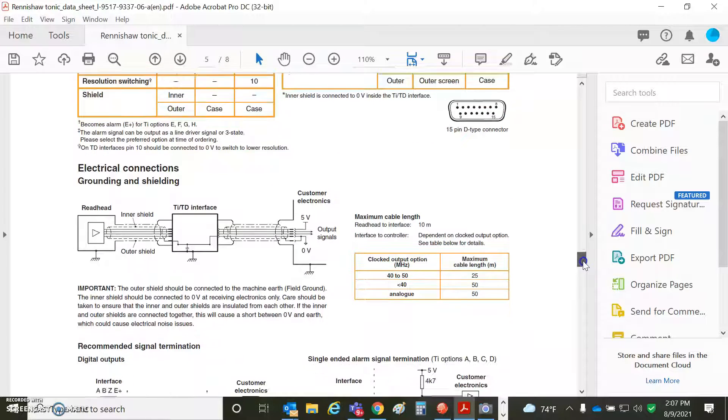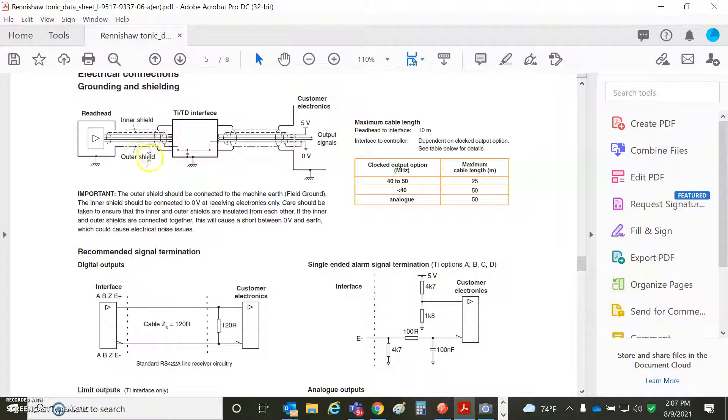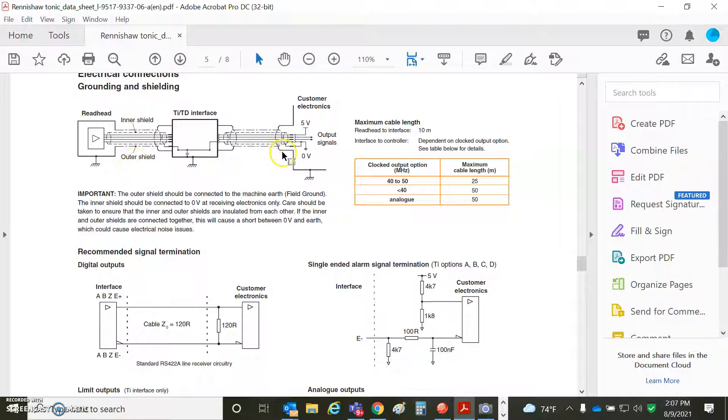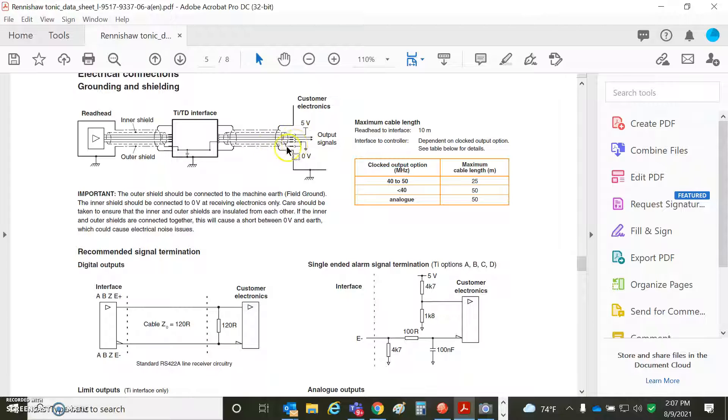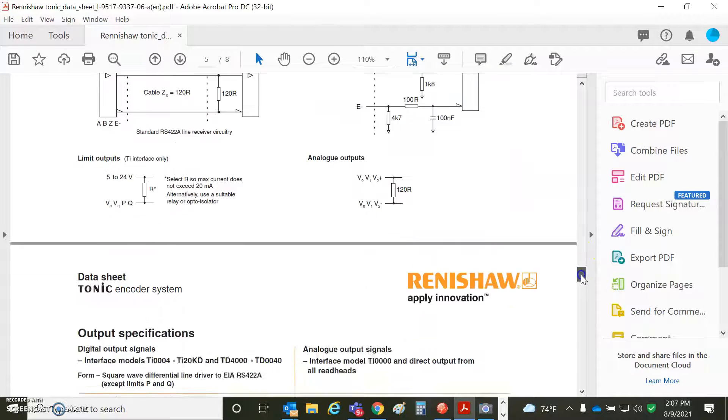There's a limit to the speed based on the resolution. But I think the important thing for these little stages is good shielding. So there's an outer shield goes to frame or earth. And then the inner shield, that can go to zero volts, the same as the five volt supply return. So two shields, inner shield goes to zero volts, outer shield goes to earth, make sure all shields find a path to earth. That's important.